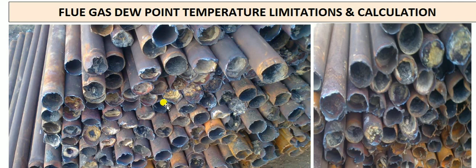Cold end corrosion will take place whenever the flue gas temperature is below the dew point. Condensation will take place. That is, acid dew will form over the surfaces, the duct surfaces and the tube surface, which will get corroded and thin out the tubes. Due to the blockages, we have more pressure drop across the furnace and across the tubes, creating high furnace pressure.